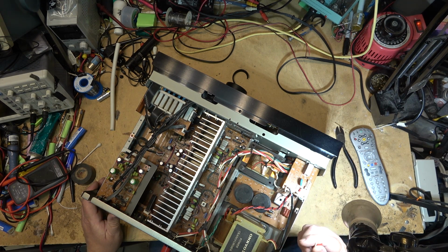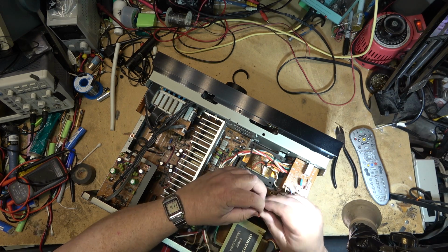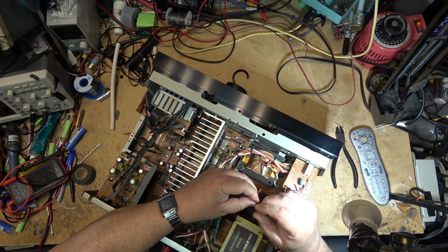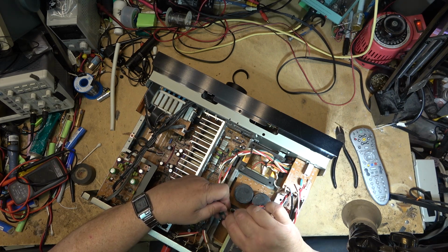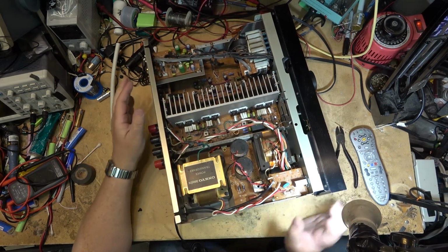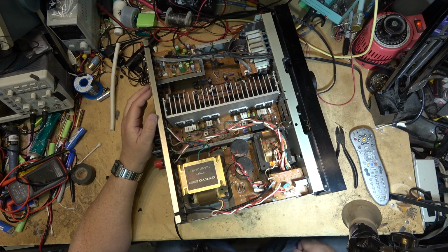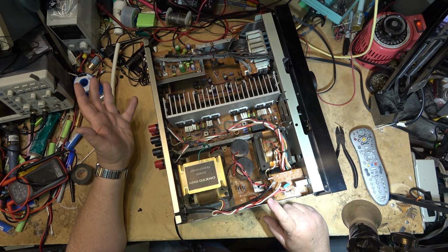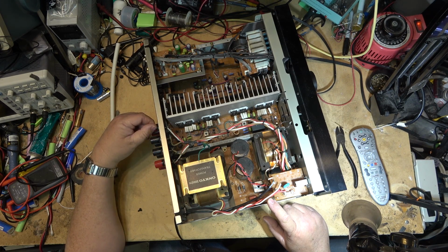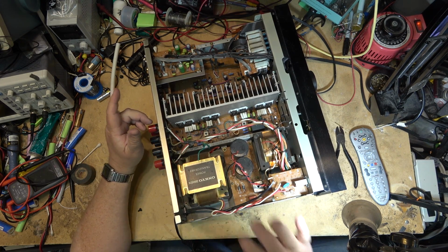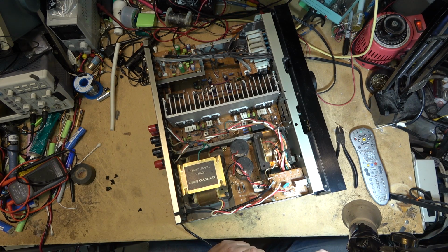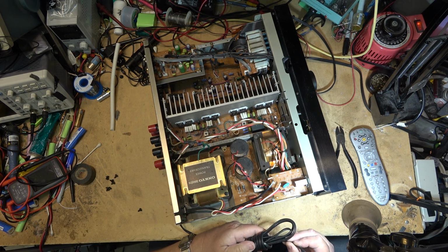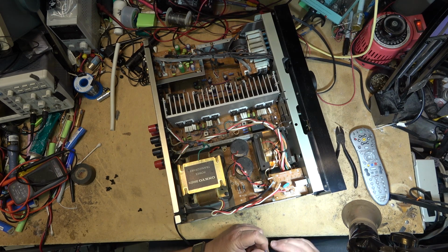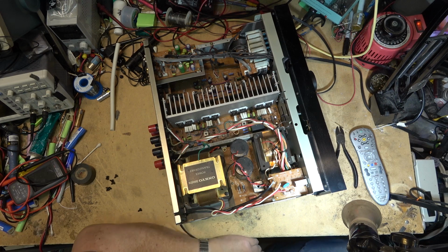I can power this up off of 120 volts, and measure what the power is on these wires, and that will tell me what secondary voltage I need on another transformer, and hopefully this other one I've got here will be close. If it's close, it'll work, as long as it's not higher than what this one is. And again, if I power this up on 120 volts, the voltages will be half of what I need, because running at 120 volts gives half the voltage on the secondary.